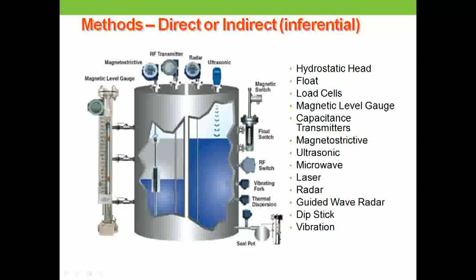All right. Next, considering the different RF transmitter medium, radar medium, and ultrasonic mediums. This is an ultrasonic medium which measures the liquid level with respect to sound signals. When the water is filled from the top end onwards, the level rises here, and how far the level has risen will be tracked. We have already discussed that ultrasonic exists with a sensor called a transceiver or transducer. Transducer is also a type, and in that subtype, there is the transceiver, transmitting the sound signals and receiving those signals simultaneously, indicating the water level that has been filled within that tank, and it displays on the screen. Here we will be loading hydrostatic heads, floats and load cells, the components utilized for this beaker. We'll look into this in depth presently.